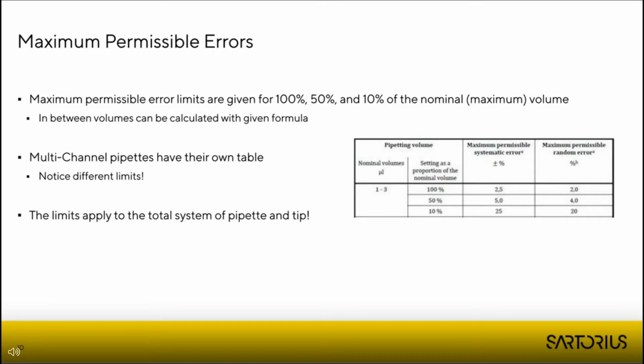Multi-channel pipettes used to have twice the limit of single-channel pipettes, but now there is a new table just for multi-channel pipettes. And that's a welcome addition as well. So multi-channel pipettes have their own table now. The limits are different compared to single-channel pipettes, but they are not twice the amount they used to be, which is good for the user.